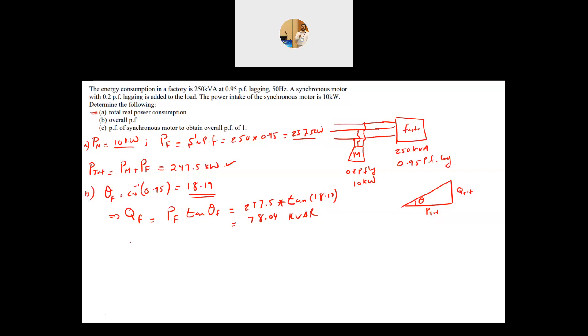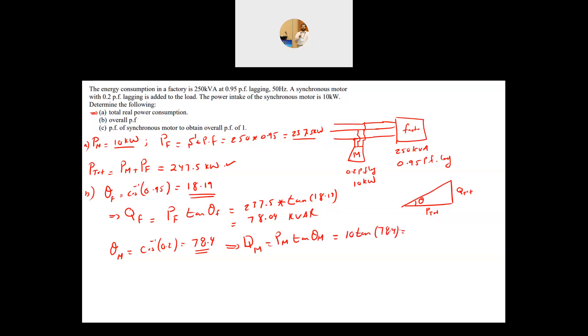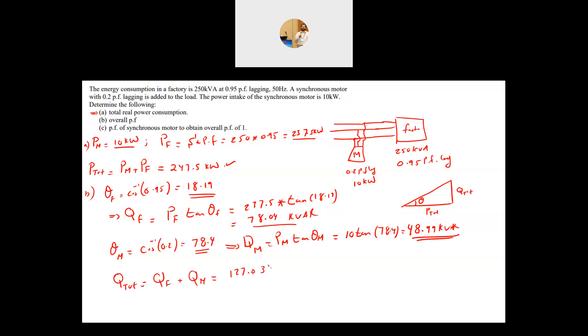That gives Q_factory equals 78.04 kVAR. Now for the motor: theta of the motor equals cosine inverse of 0.2, giving 78.4 degrees. Therefore Q_motor equals P_motor times tan(theta_motor), which is 10 times tan(78.4 degrees), giving 48.99 kVAR. The total Q is Q_factory plus Q_motor, which is 127.03 kVAR.